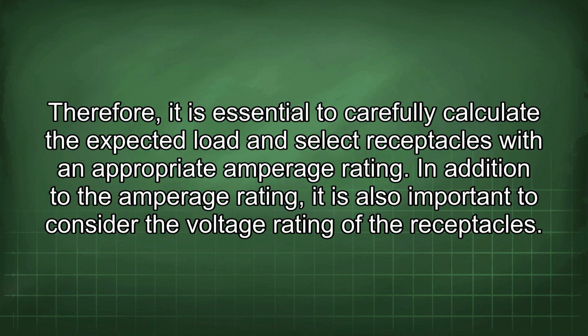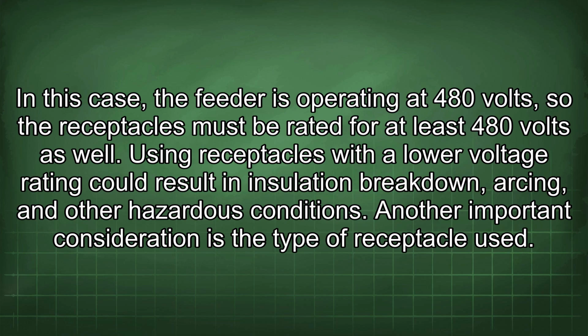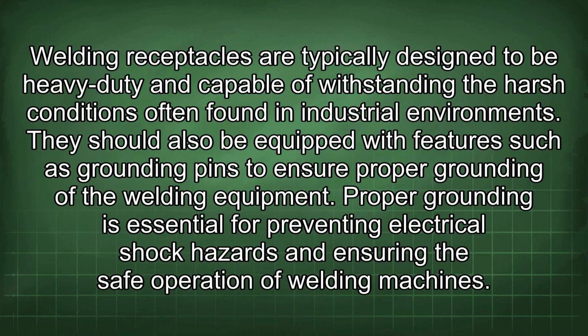In addition to the amperage rating, it is also important to consider the voltage rating of the receptacles. In this case, the feeder is operating at 480 volts, so the receptacles must be rated for at least 480 volts as well. Using receptacles with a lower voltage rating could result in insulation breakdown, arcing, and other hazardous conditions. Another important consideration is the type of receptacle used. Welding receptacles are typically designed to be heavy-duty and capable of withstanding the harsh conditions often found in industrial environments.